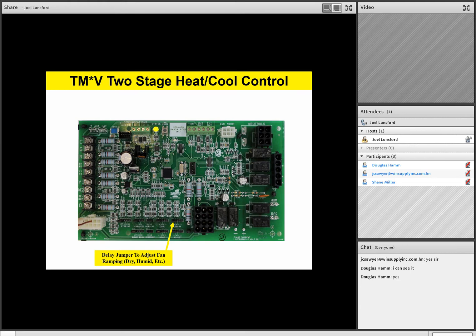Okay, the next two jumpers actually work together. The adjust jumper and the cool jumper work together to adjust cooling airflow for Y1 and Y2 input. So on my control board, if I have a Y1 and a Y2 input from the thermostat, the control board is going to look at the position of those jumpers, cool and adjust, to determine how much airflow it's going to push for first stage cooling, second stage cooling, Y1 and Y2.